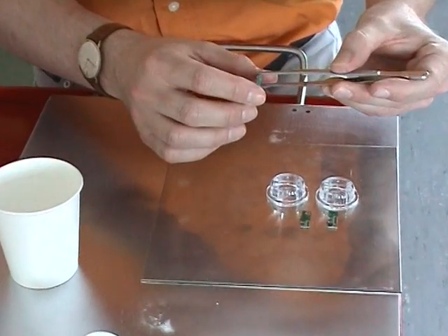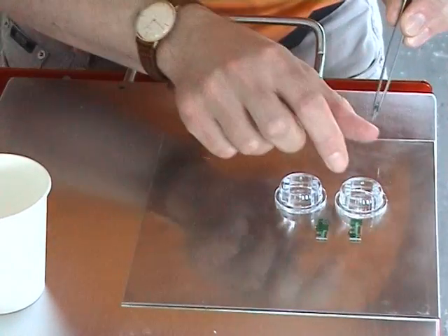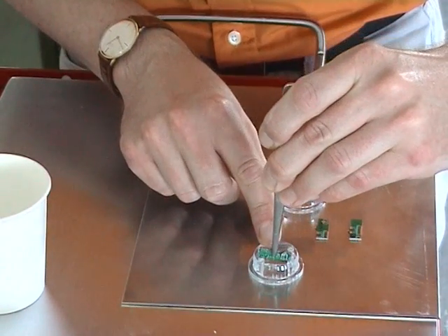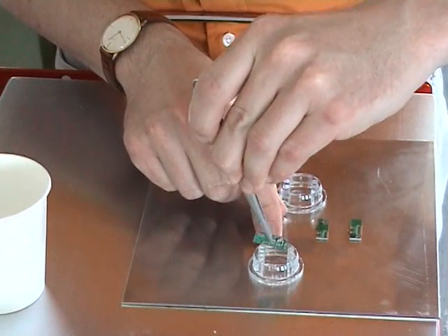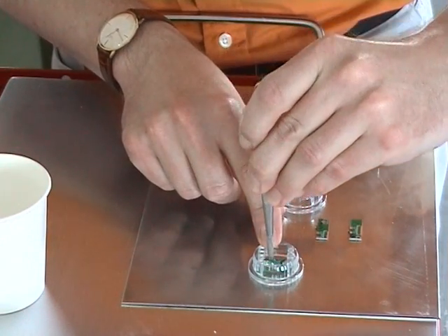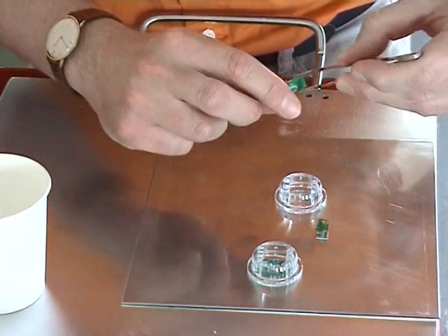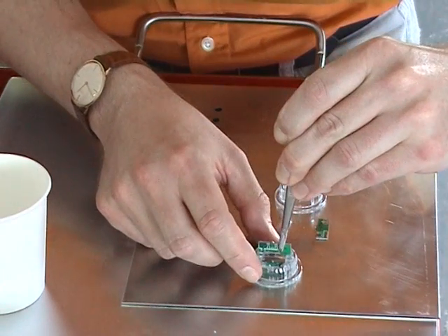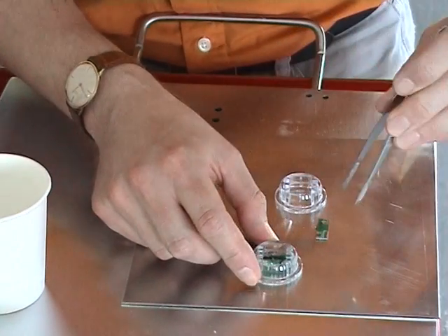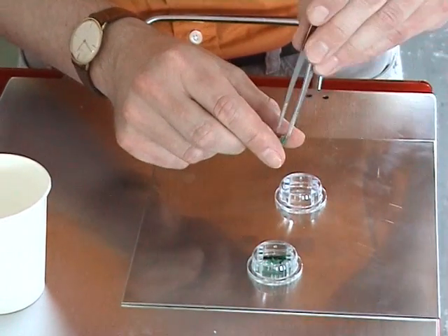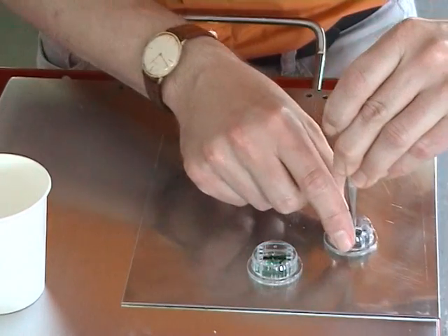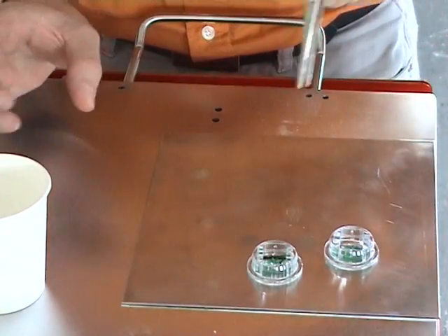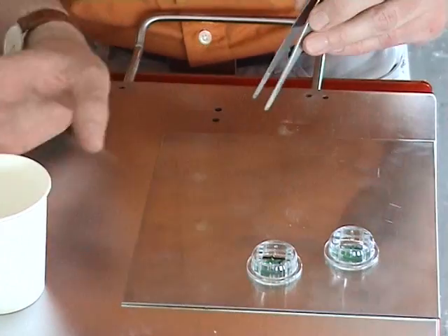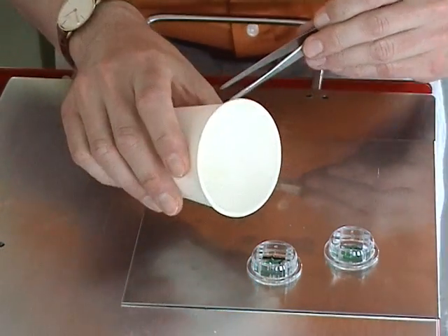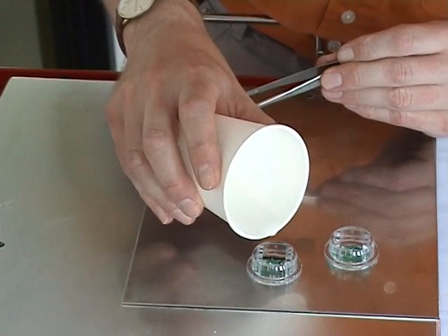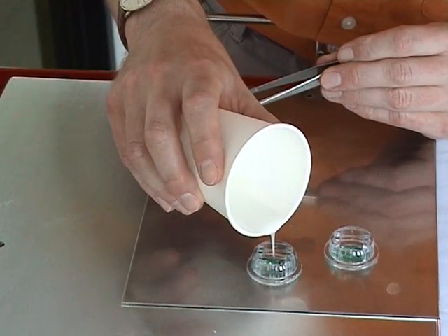Choose the appropriate specimen holder depending on the specimen thickness. Up to 4 specimens can be put in one holder. Fill in the liquid carefully so that the specimen is embedded.